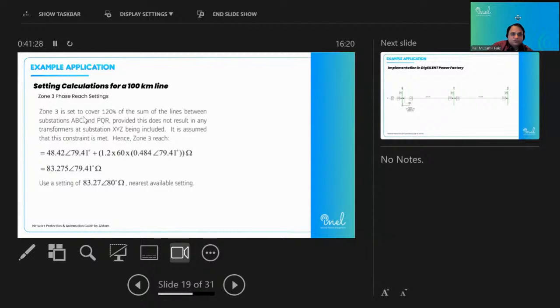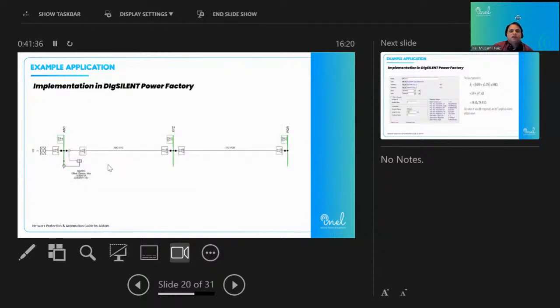So this is the zone 3 setting, and we have calculated it as 83.275 with an 80-degree angle. And this is the implementation in PowerFactory. I have modeled this network like this: this is a 60-kilometer section, this is a 100-kilometer section, and I have a relay at the ABC point. This is the ABC location, this is XYZ, and this is PQR.